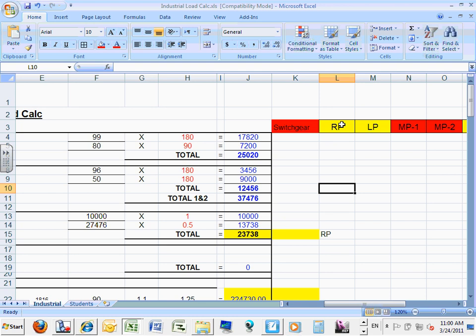No, you don't want to do it 9 times. So what I would do for neutral: anything 225 amp panels or lower, full neutral. Don't even mess with it. If you go higher than 200 amp, cut the amount above 200 amp by 70%, and then add 200 amp to it. You want to see how I'm going to do it in a second.